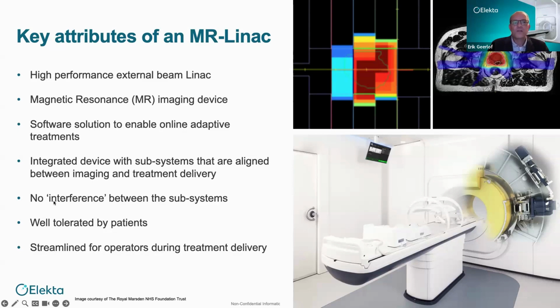Then we need, obviously, where the LINAC and the MR scanner are coming together, no interference between these subsystems. So there should be no interference between the MR scanner and the LINAC. And I think that was one of the biggest challenges for everybody involved developing an MR-Linac, because we all know that the two devices, a Linac with high energy and an MRI scanner with a high field strength, basically don't work together. So they had to come up with a lot of technical physics solutions to make that happen.